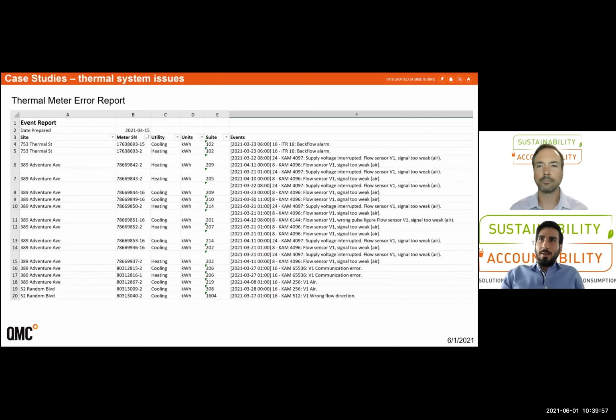And as I mentioned earlier, we preferred digital communications from the meters, as they would offer more value and more variables out of each meter. One of the common issues when it comes to thermal metering, where most of the flow meters are using 24 volts power, supplied either by a transformer within the fan coil, or a transformer that is installed separately serving the meter.